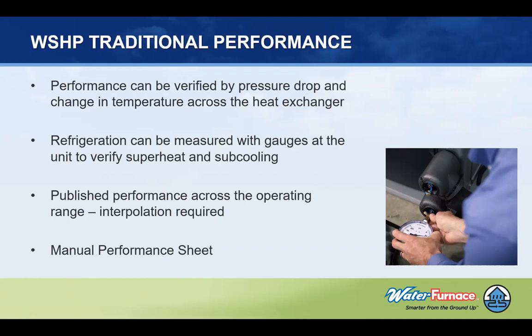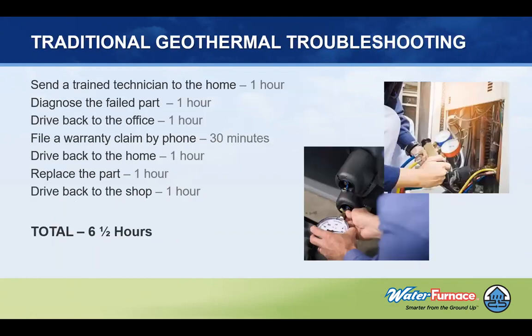You also can get refrigeration by putting gauges on the system to get your superheat and subcooling, which is obviously standard for every HVAC system in the market. The goal of this was to make it so that you didn't have to go to that extra work of getting to the unit to understand the performance of that piece of equipment.